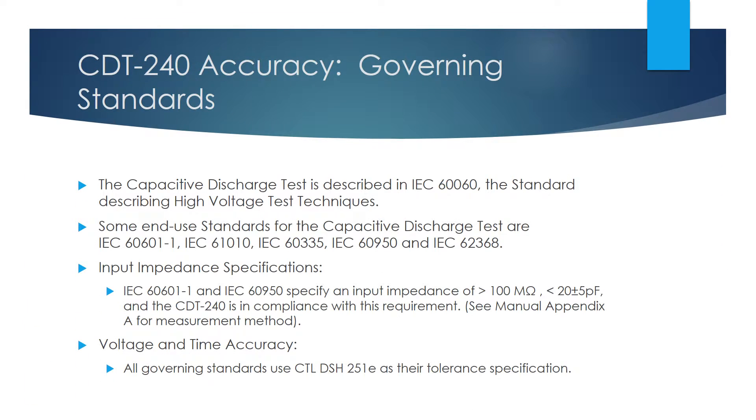The Capacitive Discharge Test is described in IEC 60060, the standard describing high-voltage test techniques, and also in many end-use product standards. The test sets criteria for voltages that can exist on the plug blades when a product is unplugged from the wall. IEC 60601-1 Medical Equipment and IEC 60950 Data Processing Equipment have an input impedance requirement of impedance greater than 100 MΩ and capacitance of 20 ± 5 pF. The CDT240 is in compliance with this requirement. Please reference our manual for further information on this point.